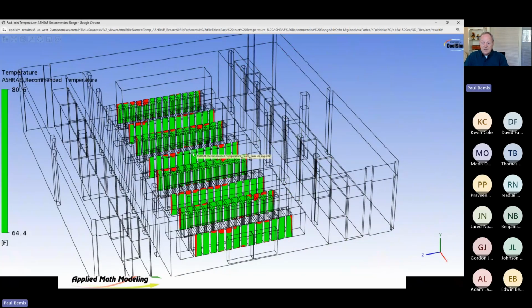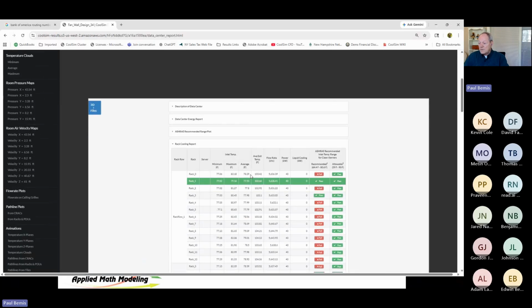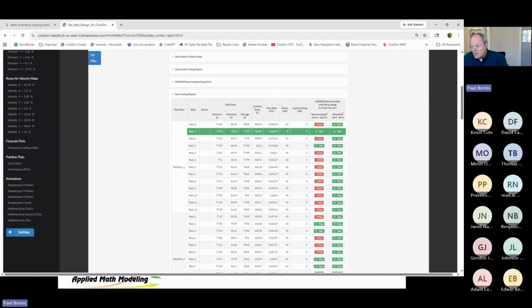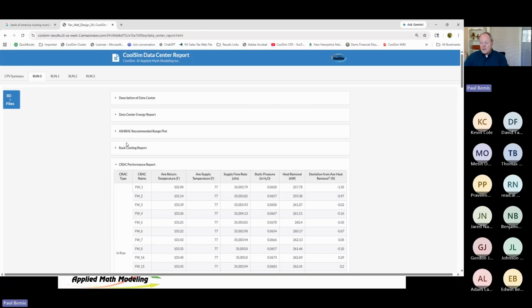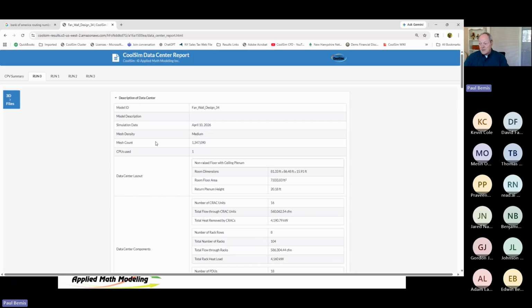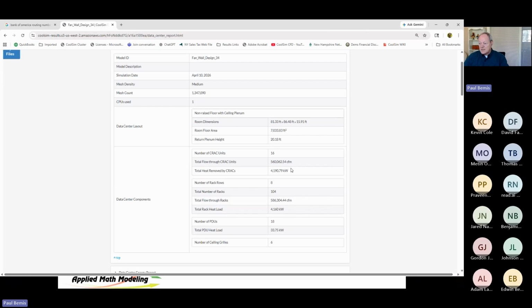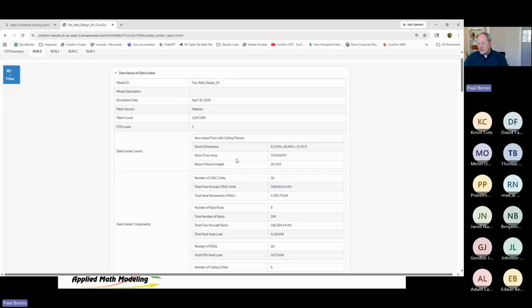You're not going to be able to run these things at the rated capacity that you've got them at. Right now, we've got them sitting there at 40 kW each. 40 kW of air cooling, that's about the upper limit for these kinds of designs. It gets difficult to get enough air in the room. If you take a look at what we're pumping in there, we're pumping in 560,000 CFM of air into a room that is only 7,000 square feet. That's a lot of air.